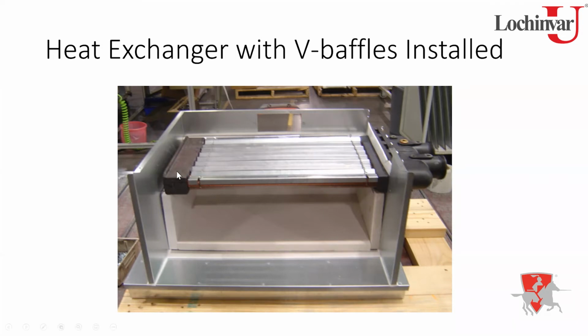You've got a couple of brackets here that just hold those V-baffles in place. Those are primarily shipping brackets. Once you get it on the job site, if you took those off, no big deal. You don't necessarily have to have them for the operation. If for some reason we do have to clean the heat exchanger, because it's fairly dirty at this point, you do want to pull those baffles off to get to the top of the heat exchanger. Make sure you brush that copper off really good. Vacuum it out. Primarily, you're going to use a stiff bristle brush. Whatever you do, don't use a wire brush or wire wheel on the copper because it will damage the copper.